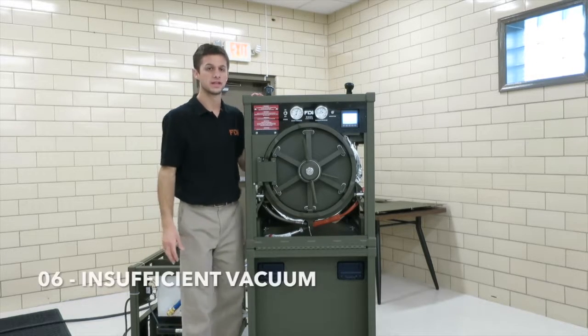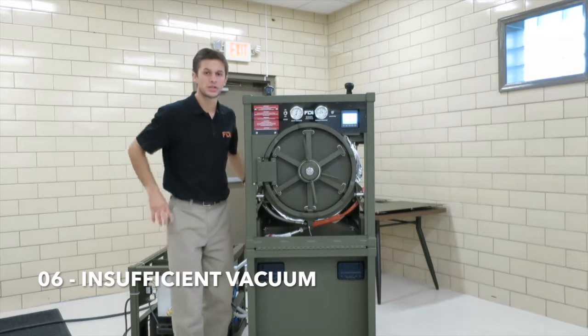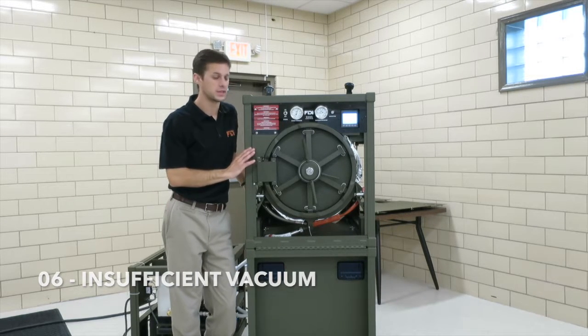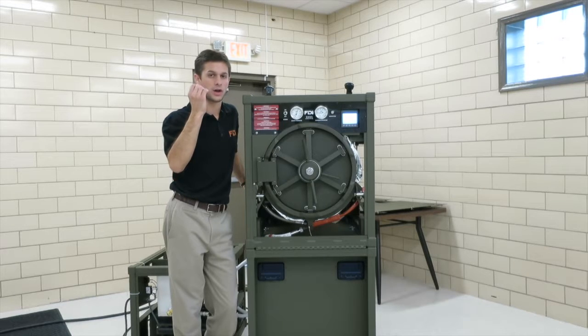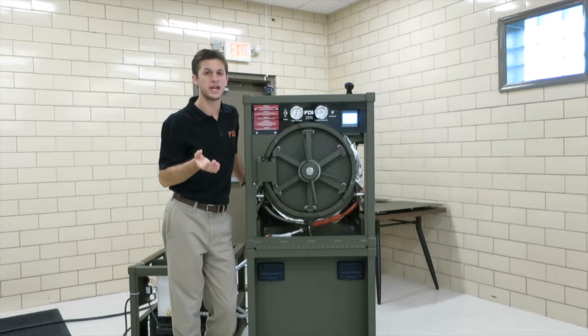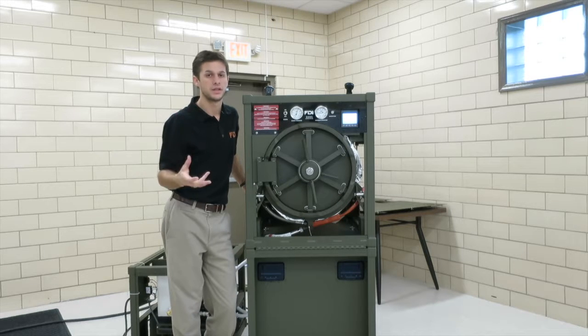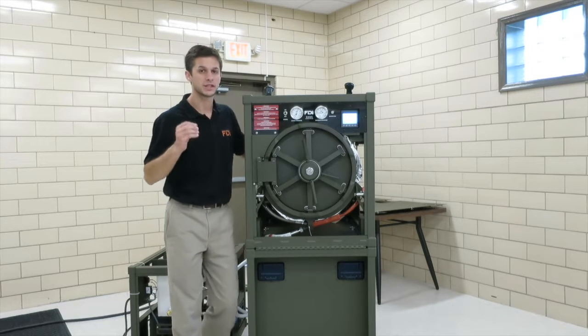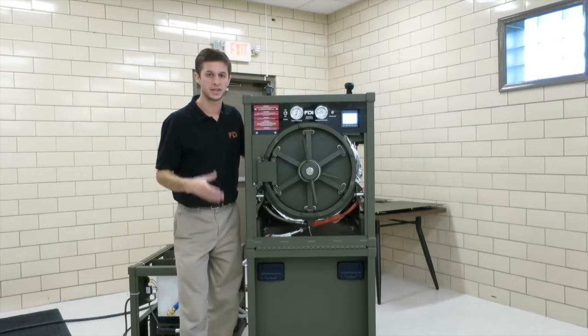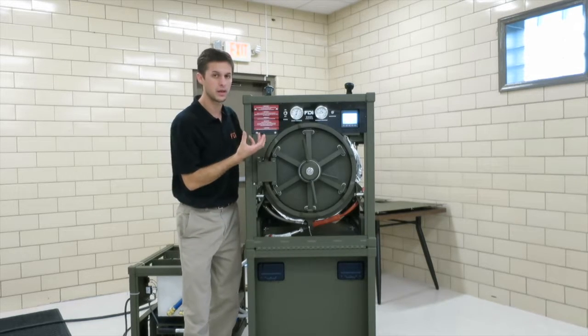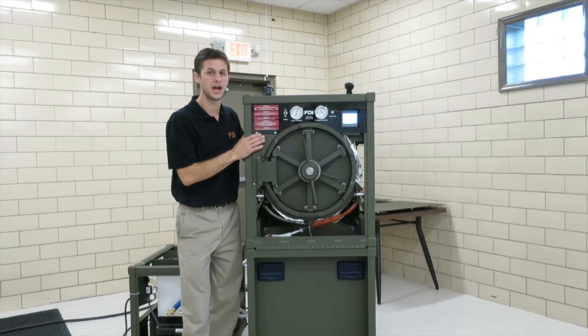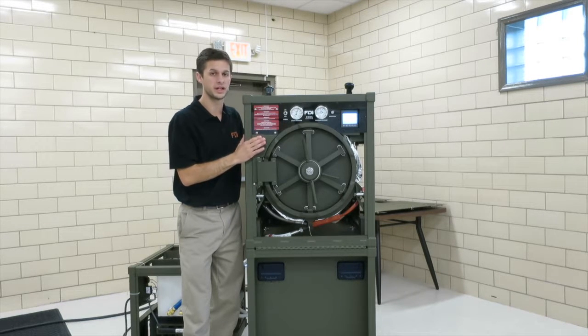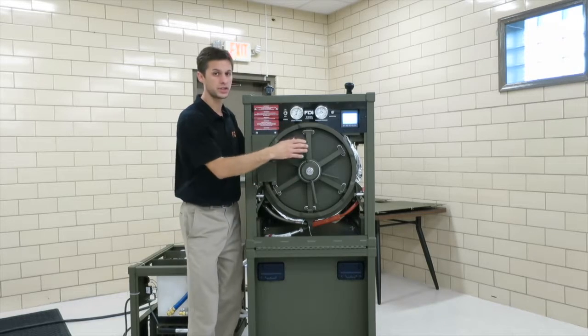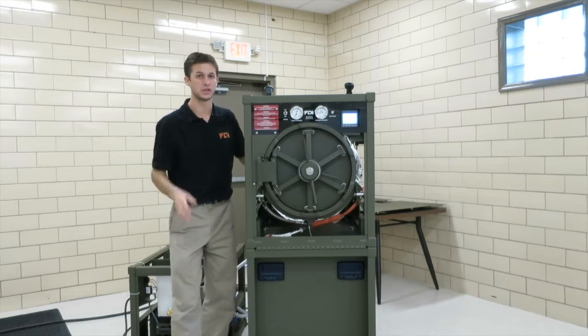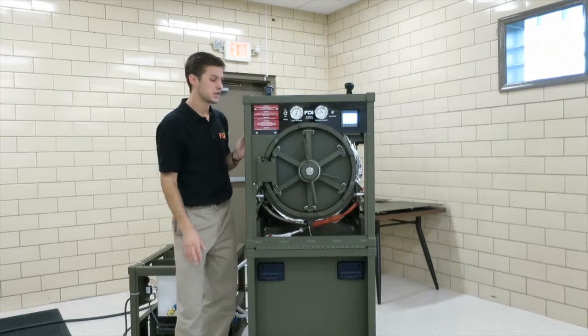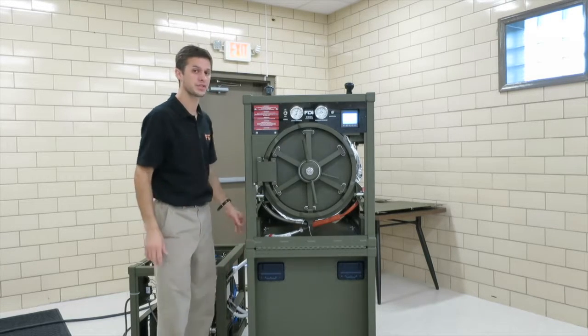Number 6 is insufficient vacuum. This is for the conditioning phase. During the conditioning phase, when we are pulling our 3 vacuums, the first one's 10 inches of mercury, then 14, then 18. If it can't get to those set points within a certain amount of time, again, it's a timer watching it. It gives the sterilizer a certain amount of time to get to those set points of 10, 14, and 18. And if it can't get there in a certain amount of time, the PLC will throw this insufficient vacuum alarm. So you could have some problems with your water recovery system.